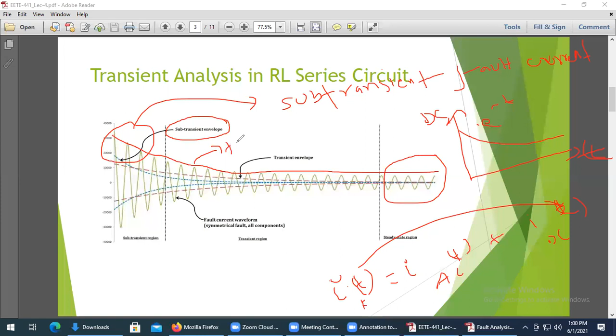The reduced magnitude of the fault current after the subtransient period is called the transient fault current. At the very beginning, the fault current will be maximum. It will continue to flow, sustaining for at least up to half a cycle. Then the magnitude of the fault current will start reducing, and it will reach another period, normally called the transient period. So you already have two periods and two types of fault current. One is the fault current of the subtransient period, called the subtransient fault current, denoted by IF double prime.